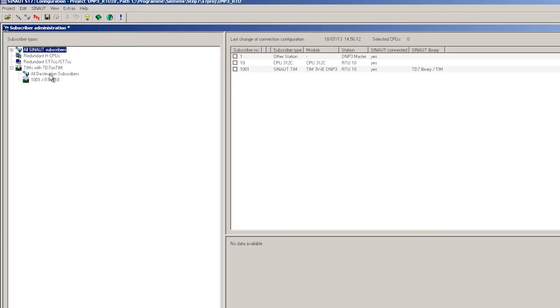First of all, we set the DNP3 conformity level. We select level 5 to ensure that we can use the greatest possible range of functions with respect to data buffering and timestamp.